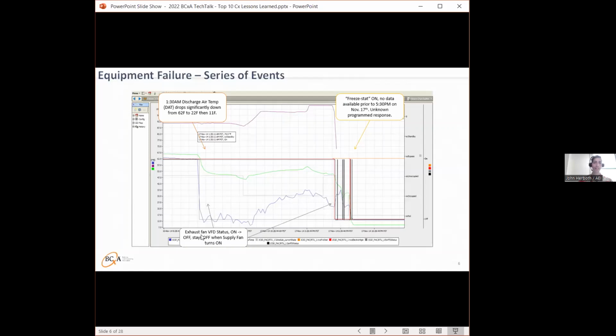Well, if you look at the bottom left, the exhaust fan's VFD status says on, but it stays off when the supply fan turns on. Oh, the exhaust fan failed. So there was some sort of thermal relay that overheated.